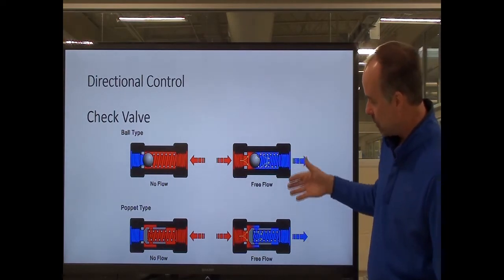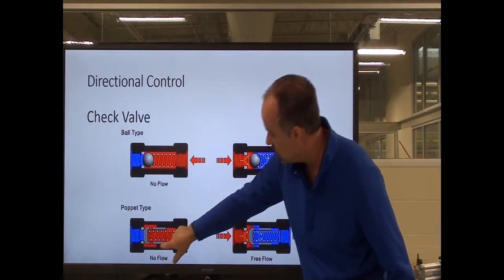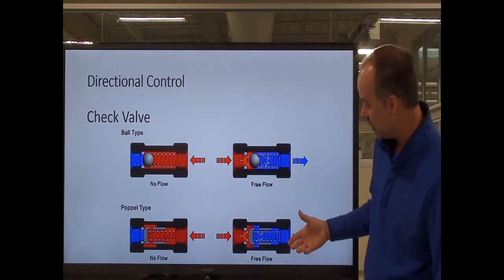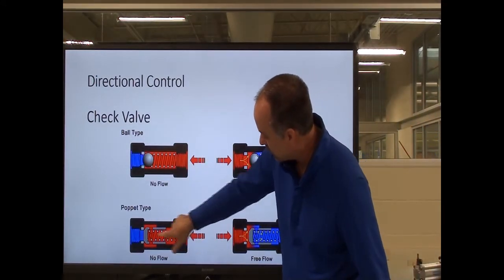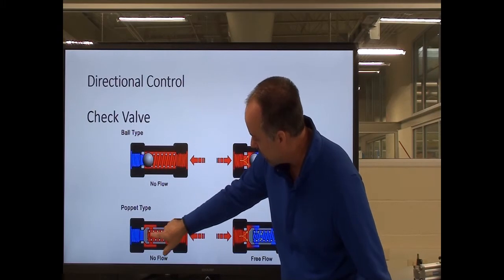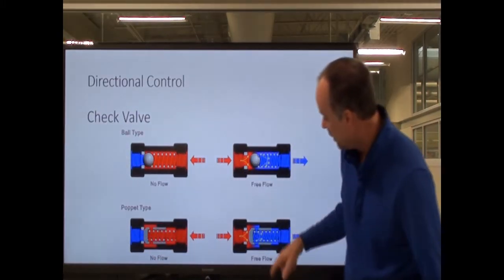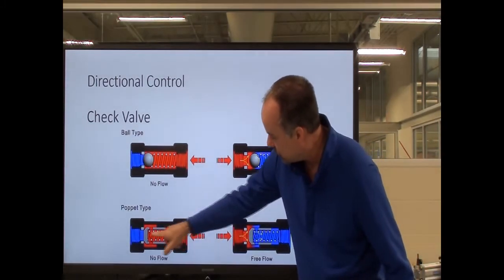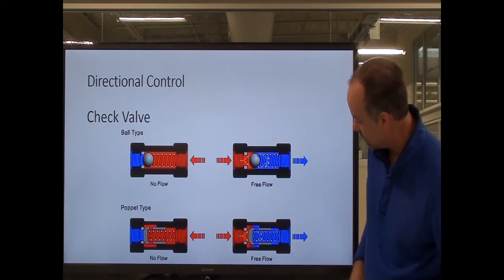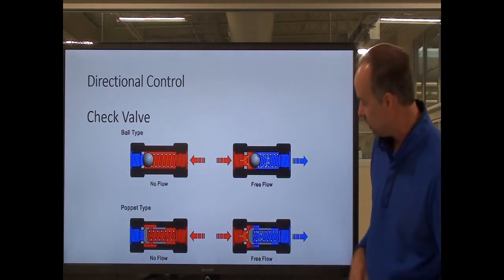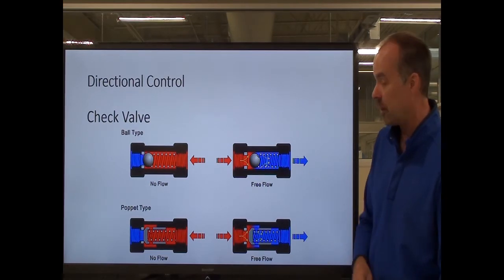The difference between a ball and a poppet type: with a poppet, you've got a different shaped type of valve. It performs the same function. I've got a spring and the poppet actually creates a seal through the orifice. When I push fluid one way, it seals it off, and fluid coming back the other way will push that poppet back off of its seat and allow fluid to flow. Just a different design, but it performs the same function.